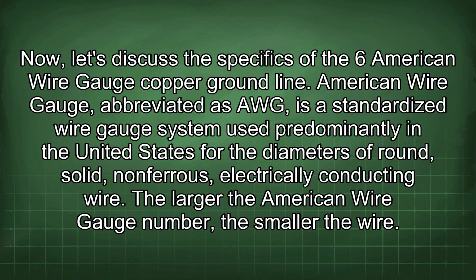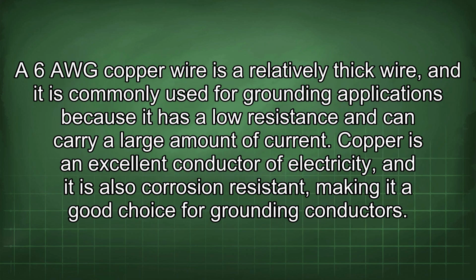American wire gauge, abbreviated as AWG, is the standardized wire gauge system used predominantly in the United States for the diameters of round, solid, non-ferrous, electrically conducting wire. The larger the American wire gauge number, the smaller the wire. A 6 AWG copper wire is a relatively thick wire, and it is commonly used for grounding applications because it has low resistance and can carry a large amount of current.